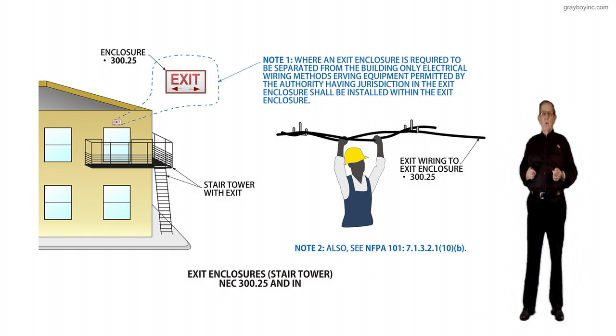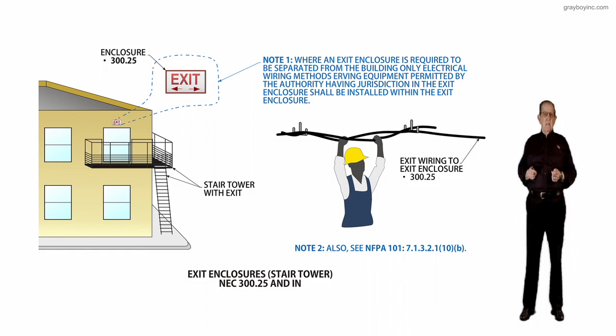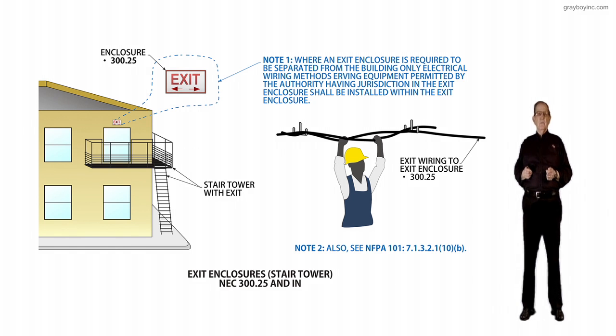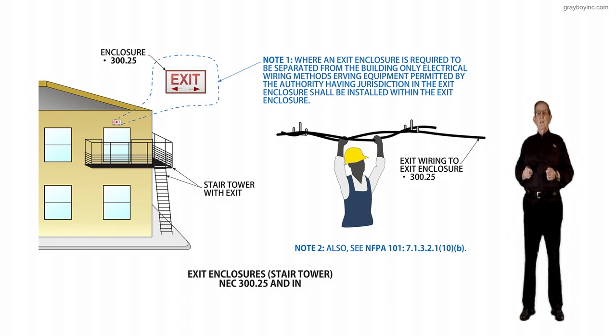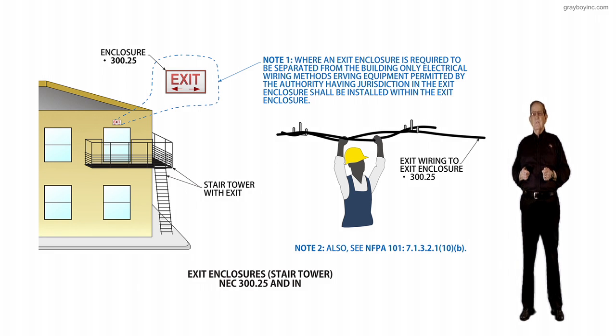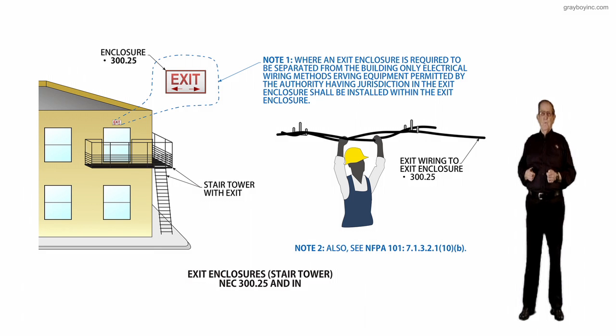The mandatory text in NFPA 101, Section 7.1.3.2.1 item 10b, states the conduit restriction. However, the explanatory text in Annex A7.1.3.2.1 item b states that provisions for electrical wiring are permitted where the wiring system's equipment is permitted by the authority-having jurisdiction to be located within the exit enclosure, such as security systems, public address systems, and fire department emergency communication devices.